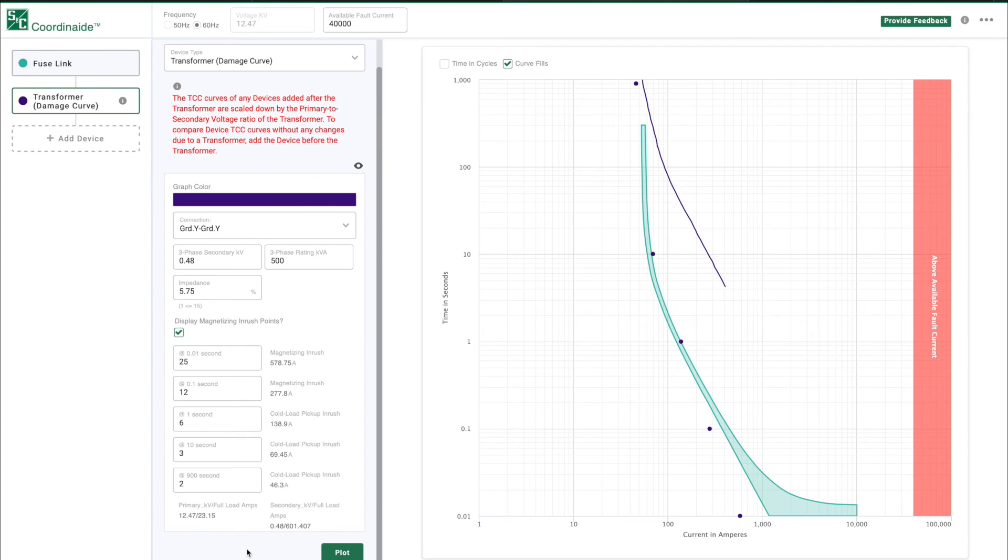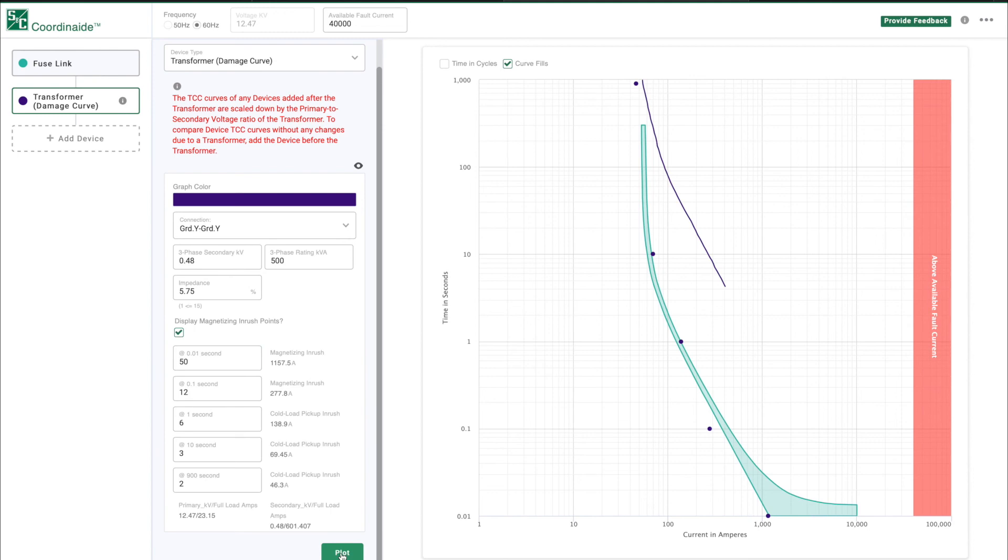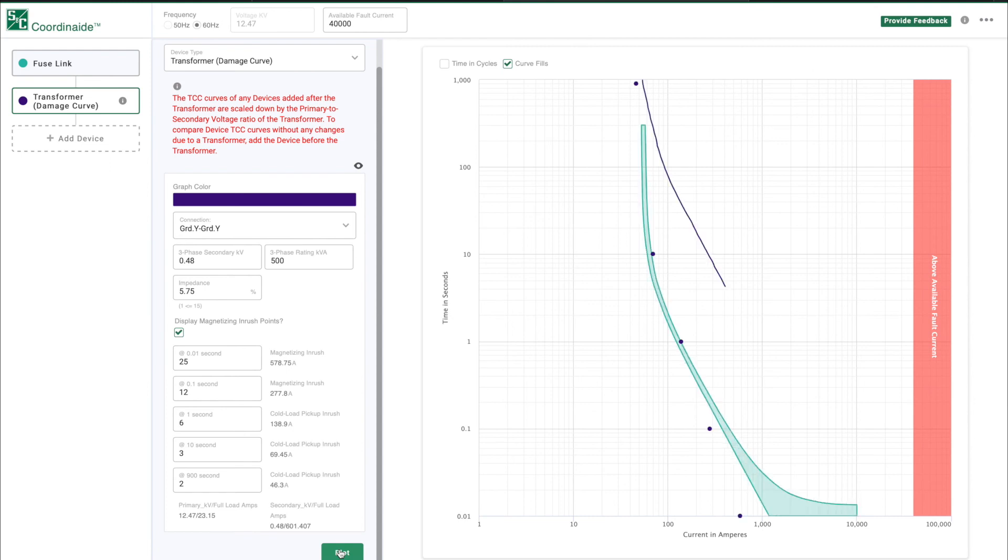The magnetizing and cold load inrush points are calculated using industry standard multipliers of transformer full load current. These multipliers can be changed by simply entering new values in each field. When you click on the Plot button, it will apply the new multipliers. With the inrush points plotted, you now have a more complete picture to evaluate transformer protection.